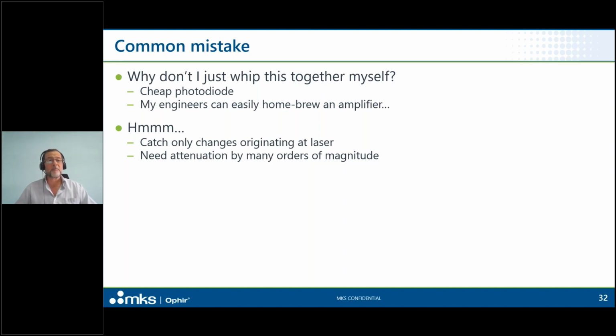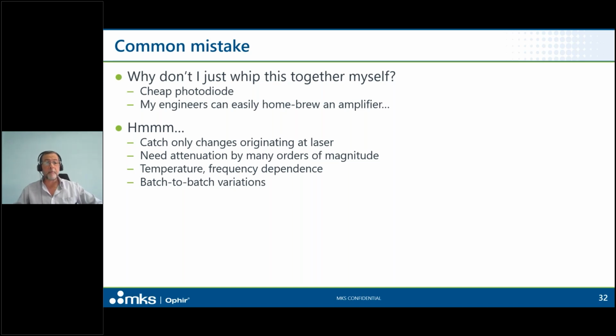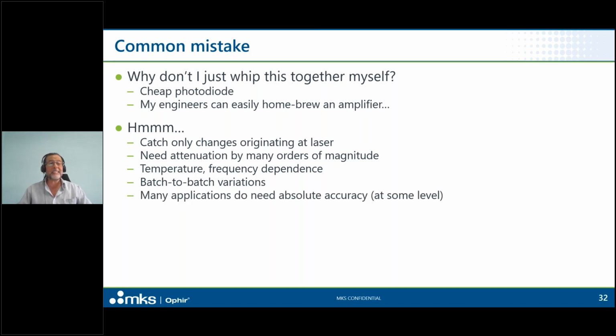I'm going to need to account for the fact that the photodiode sensitivity is affected by temperature, semiconductor physics. It's affected by the pulse frequency if I have a pulsed beam. There are going to be batch-to-batch variations if I'm ordering bags of photodiodes by the kilo. I'm going to need to calibrate for those variations. And we're talking about medical applications. In not all, but in many cases, as we saw, I'm going to need to be able to quantify the absolute accuracy with which I'm making these measurements.